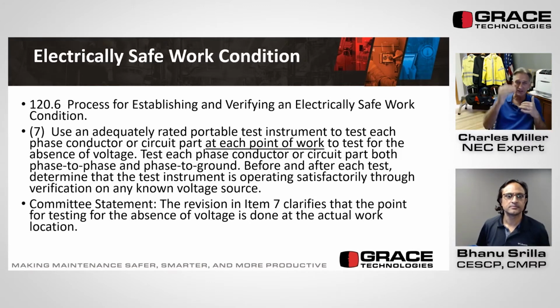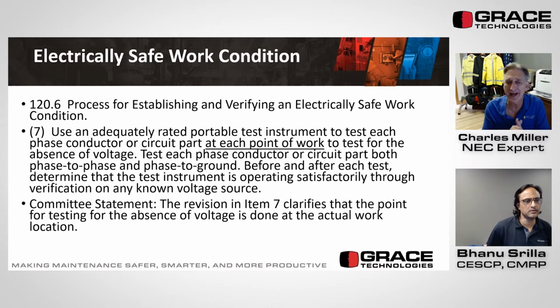We've got six steps before this one, and it says to use an adequately rated portable test instrument to test each phase conductor or circuit part. Before, it just said to test for the absence of voltage. Now the wording was added: test each phase conductor or circuit part at each point of work.